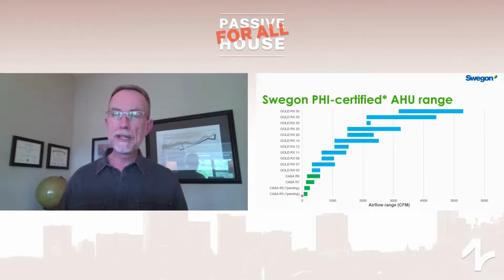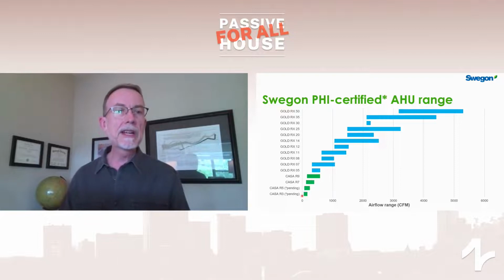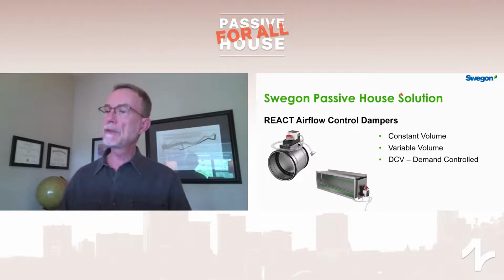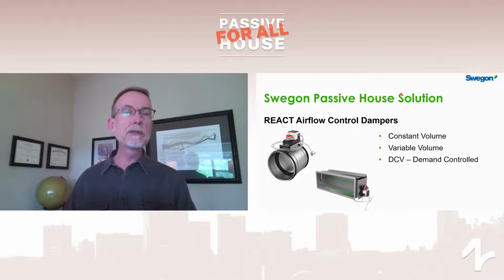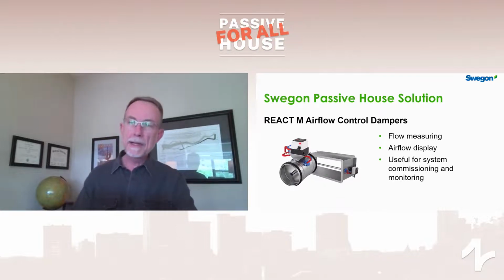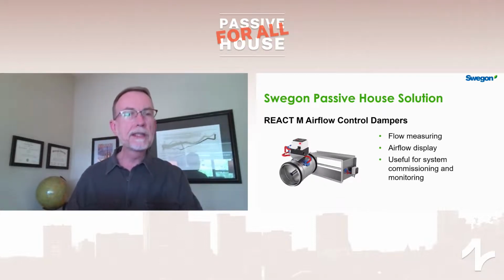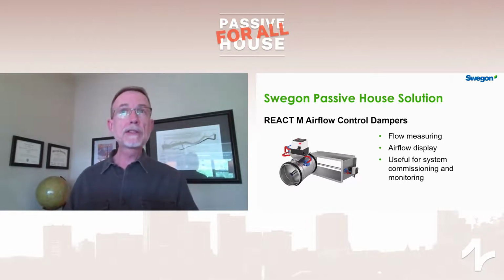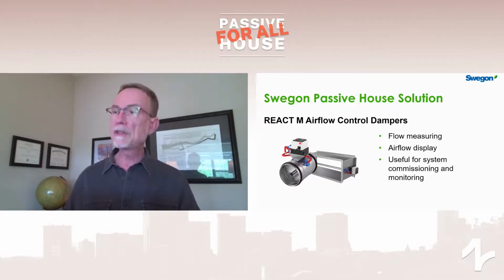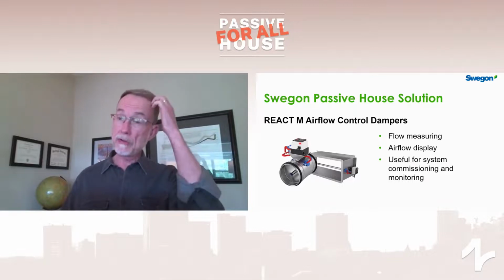Next, we have airflow control dampers. We call this product line the React line, React airflow control dampers, available to handle things like constant volume flow, variable volume flow, and demand control. The Model M, React M, is a flow measuring damper. And that is useful anytime you want to measure and monitor flow. It's also useful if you're balancing. You can use it to measure the flow and display the flow right in the zone. So the balancer can look at the output here to see and read what the actual airflow is at the moment. React P is a pressure control damper.